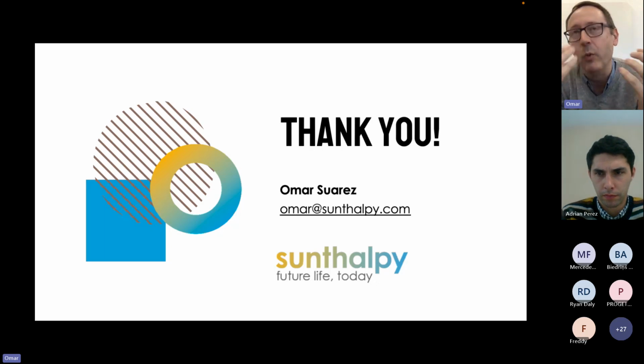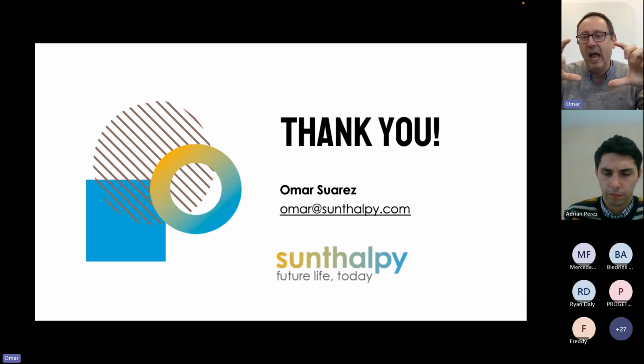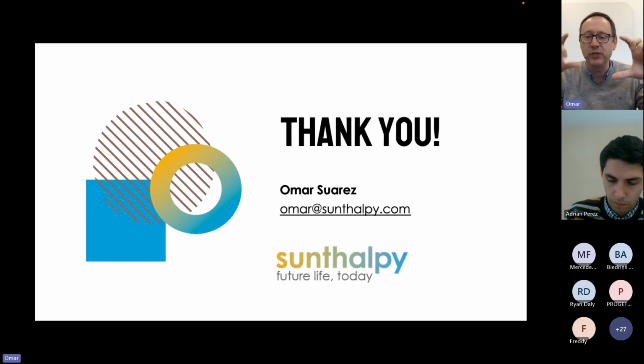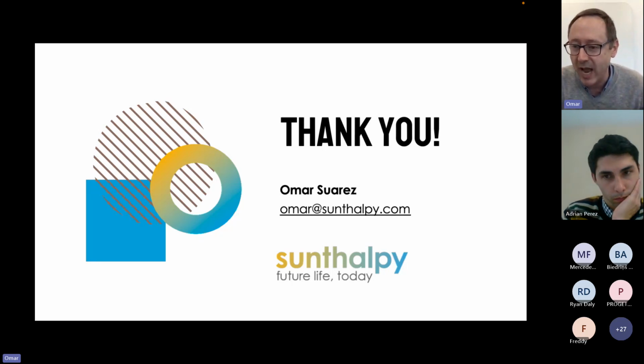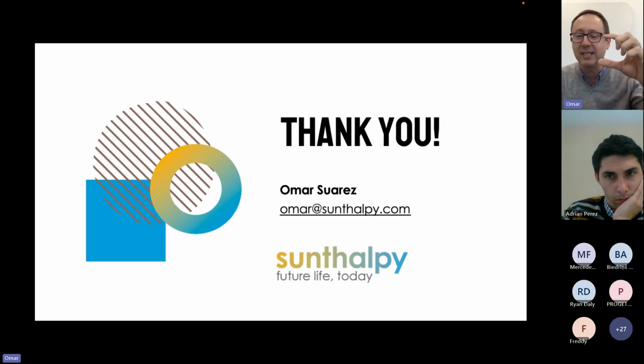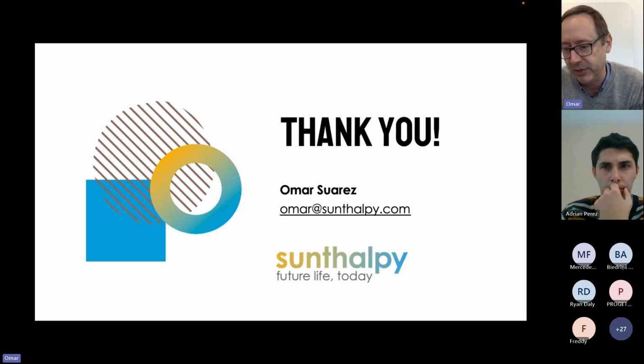What we manage to do is, when we get rid of the boiler, you're already saving the 30% of losses you lose through the chimney, leaving 70%. If we want a consistent COP of 6, dividing 70 by 6 gives you more than 80% reduction in primary energy for heating. So you get such a big reduction in electricity demand that even a small photovoltaic system would let you be net zero, if that's the objective.